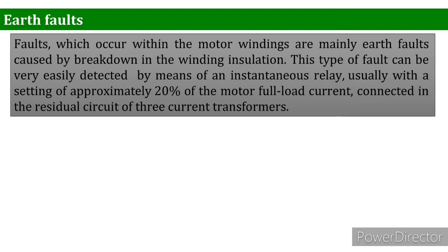Next, we have the earth fault. Faults which occur within the motor windings are mainly earth faults caused by breakdowns in the winding insulation. This type of fault can be very easily detected by means of an instantaneous relay, usually with a setting of approximately 20% of the motor full load current, connected in the residual circuit of the three current transformers. Along with that, care must be taken to ensure that the relay does not operate from spill current due to the saturation of one or more current transformers during the initial peak of the starting current, because as we know this can be as high as 2.5 times the steady RMS value.